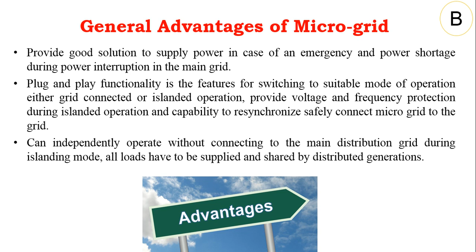The smallest islanding system that you may find is at your home if you have an inverter. Whenever the electricity grid supply fails due to a scheduled or unscheduled outage, at that time the battery-operated system will play a significant role, working in the islanding mode, and resynchronize safely and connect to the grid when the electricity returns. At that time it will provide suitable voltage and frequency and all the protection aspects. The microgrid can independently operate without connecting to the main distribution grid during islanding mode, so all loads have to be supplied and shared by distributed generation. These are the general advantages of the microgrid.